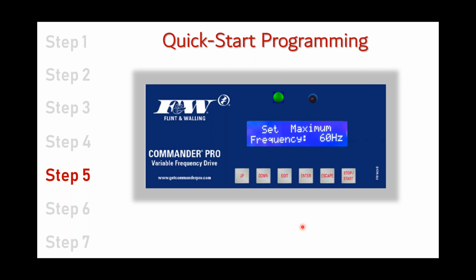But if you selected submersible like we did when we started into this programming, it's going to ask us to make this determination. Do we want to run that submersible at 60 hertz or do we want to run it at 80 hertz? If we had selected above ground pump, we get to this menu number 4. That's it. You can't change it. You would not be able to change that 60 hertz, because never ever would we want to run an above ground pump at a rating greater than 60 hertz.